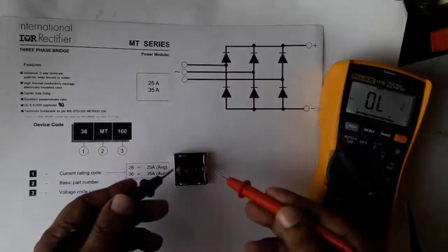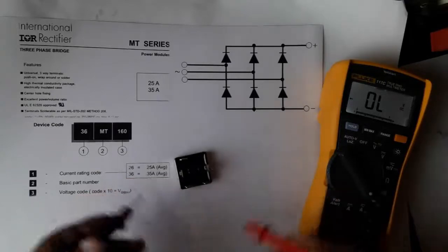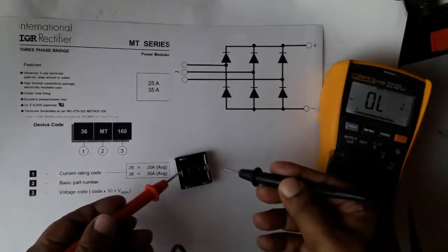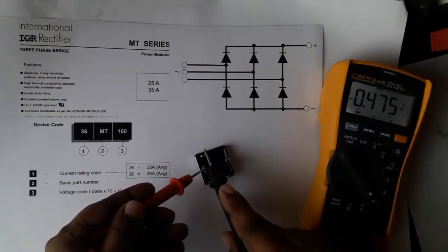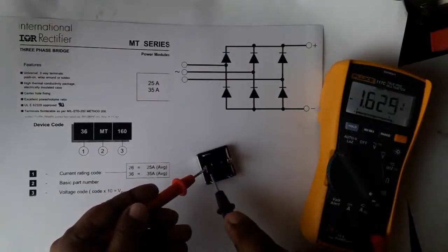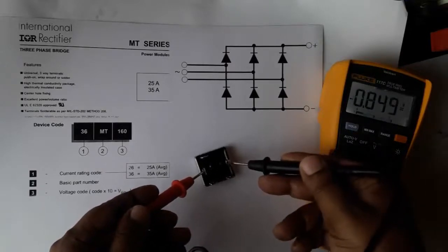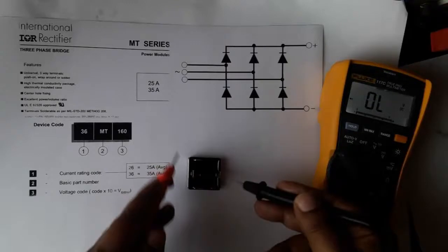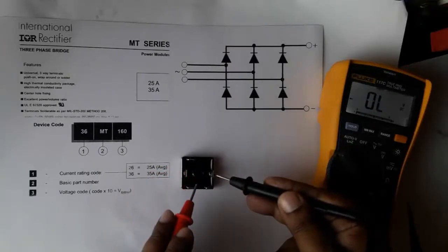Again, we're testing this rectifier by using black probe and red probe on the negative terminal and testing three phases. Now on the positive terminal, black probe testing three phases.